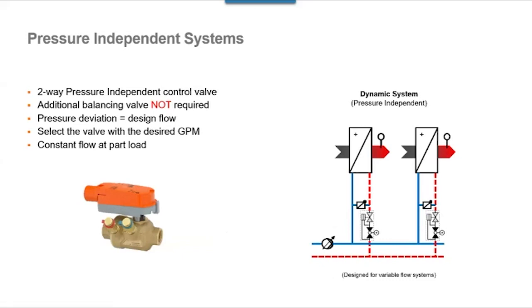We and most manufacturers will say that the minimum pressure required is 5 PSID. Some companies, ourselves included, have product that will require less differential pressure, but you also don't get as much flow from the valve. They're derated, so to speak. But as a general rule, everybody's looking at about a 5-pound minimum differential pressure. So I hope that in the past, guys were putting in modulating control valves with a 4 or 5 pound drop. I know that wasn't necessarily the case, but again, to get some authority of that valve, you want some pressure drop.